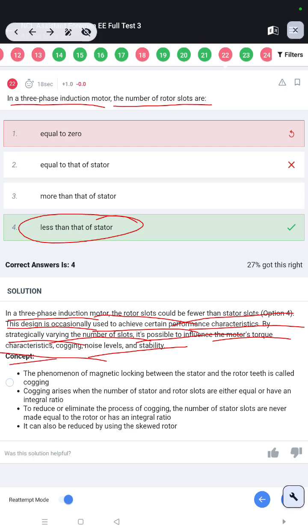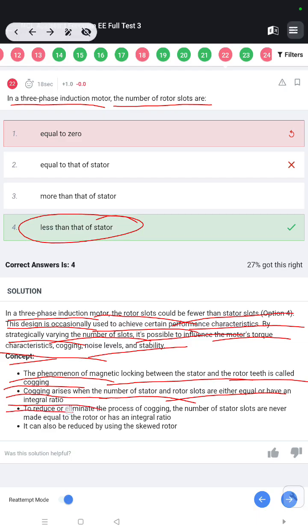The phenomenon of magnetic locking between the stator and the rotor teeth is called cogging. Cogging arises when the numbers of stator and rotor slots are either equal or have an integral ratio. To reduce or eliminate cogging, the number of stator slots is never made equal to the number of rotor slots, nor in an integral ratio. It can also be reduced by using a skewed rotor.